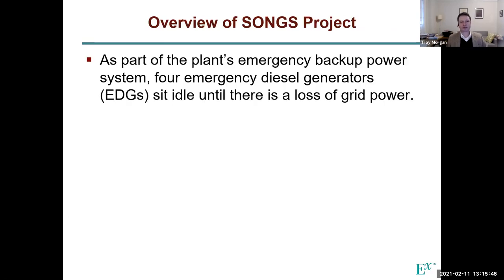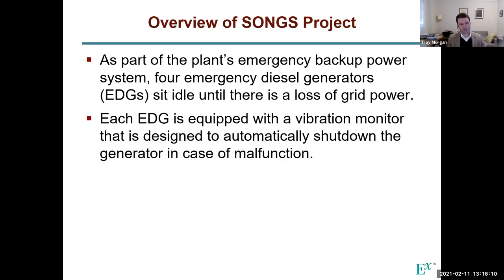So importantly, as part of the plant's backup system, there are basically four diesel generators that are just sitting idly waiting for action. You test them once a week to make sure they're operational, but otherwise they just sit there. And if there's a loss of offsite power from the grid, which powers things like pumps and other safety critical equipment, these generators kick in and provide power to those components.